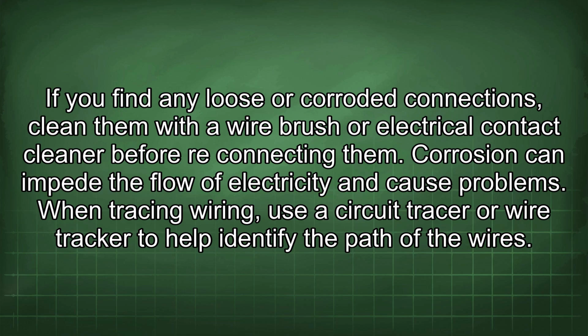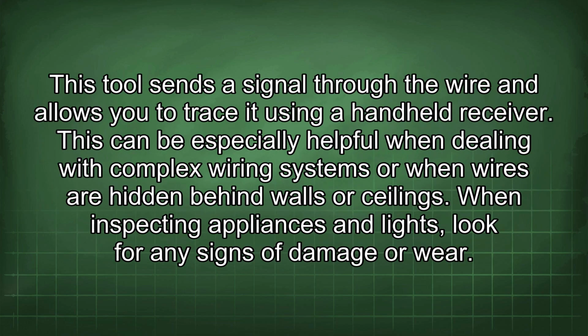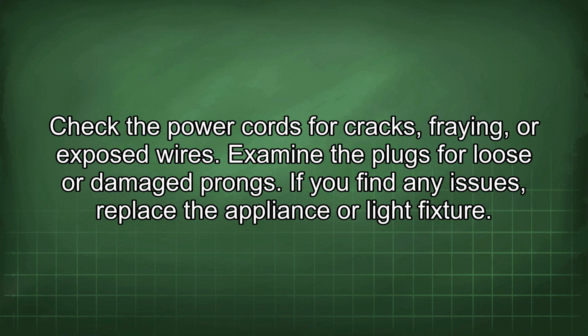When tracing wiring, use a circuit tracer or wire tracker to help identify the path of the wires. This tool sends a signal through the wire and allows you to trace it using a handheld receiver. This can be especially helpful when dealing with complex wiring systems or when wires are hidden behind walls or ceilings. When inspecting appliances and lights, look for any signs of damage or wear. Check the power cords for cracks, fraying, or exposed wires. Examine the plugs for loose or damaged prongs. If you find any issues, replace the appliance or light fixture.